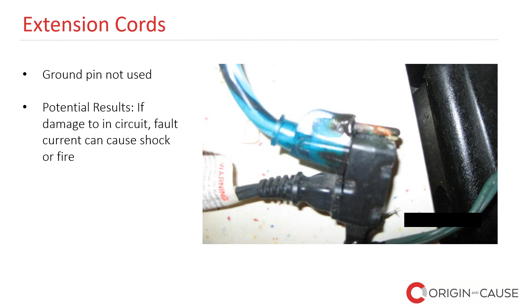Further misuse examples are hardwiring, sometimes removing the plug end of an extension cord and hardwiring it into a junction box. Now, these extension cords, or flexible cords as they're sometimes called, have certain purposes, but one of the purposes they're not intended for in many cases is permanent wiring. This type of flexible cord is specifically for temporary wiring, and this is a very likely candidate for overcurrent, overloading, overheating, and of course resulting in a fire.